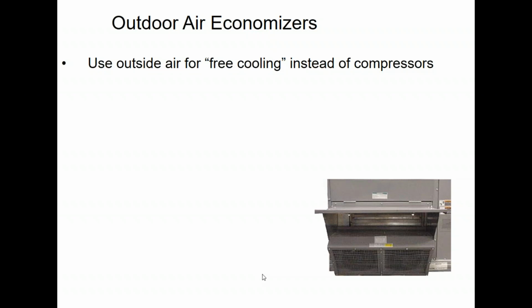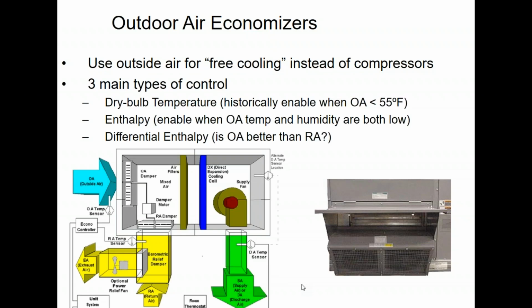There are multiple ways that we can deal with that from a control standpoint. As you likely know, the three major ways we would use would be dry bulb temperature. Historically, we've set the economizer for a 55-degree set point. If it's below 55 degrees outside, we use the economizer. If it's above 55, we use the compression. The thought process there was if I can make 55-degree air from the outside air, that's probably what my DX system was designed to supply anyway, so I'm good, right?